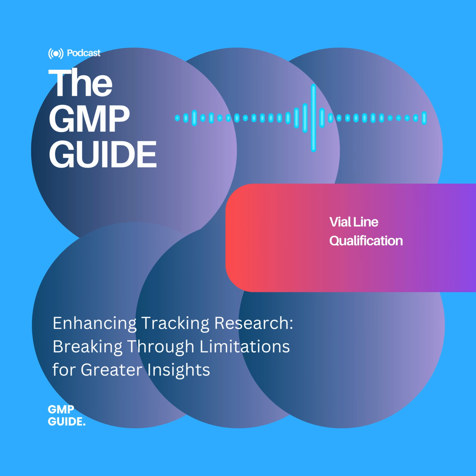Debbie Smith, BSM's VP of Quality Assurance, emphasizes that QA's role involves comprehensive oversight for all aspects of the validation plan. They're everywhere. This means rigorously reviewing and approving all pre-executed protocols for FAT, SAT, IQ, OQ for individual equipment, and PQ for the entire line. They read everything. Then, after execution, QA meticulously reviews these protocols again to ensure documented evidence of proper installation, adequate support utilities, verification of overall operating ranges, and acceptable performance. Did it actually meet the plan? This critical step ensures that the equipment meets all specifications, its intended purpose, and crucial regulatory requirements like CGMP, FDA, and EU guidelines, ultimately allowing it to be released for GMP good manufacturing practice manufacture.